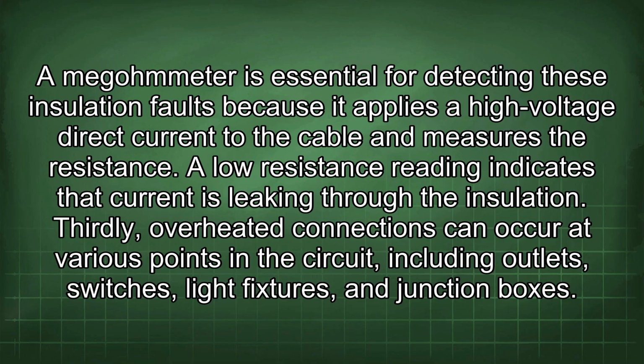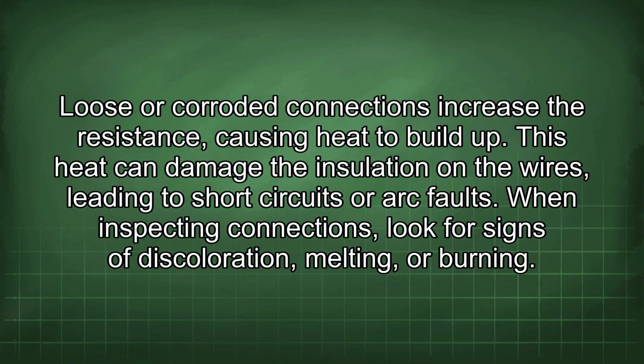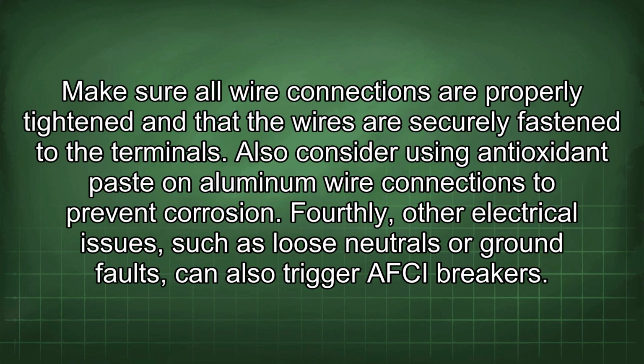Thirdly, overheated connections can occur at various points in the circuit, including outlets, switches, light fixtures, and junction boxes. Loose or corroded connections increase the resistance, causing heat to build up. This heat can damage the insulation on the wires, leading to short circuits or arc faults. When inspecting connections, look for signs of discoloration, melting, or burning. Make sure all wire connections are properly tightened and that the wires are securely fastened to the terminals. Also consider using antioxidant paste on aluminum wire connections to prevent corrosion.